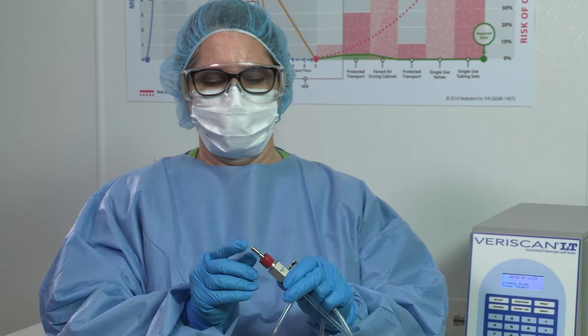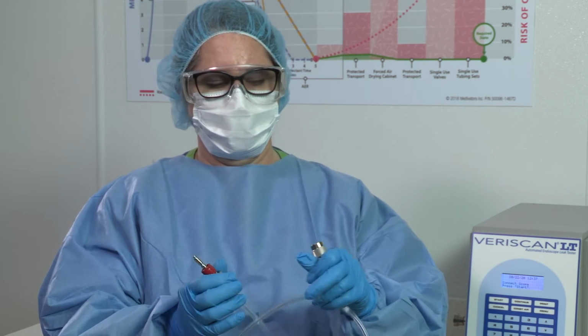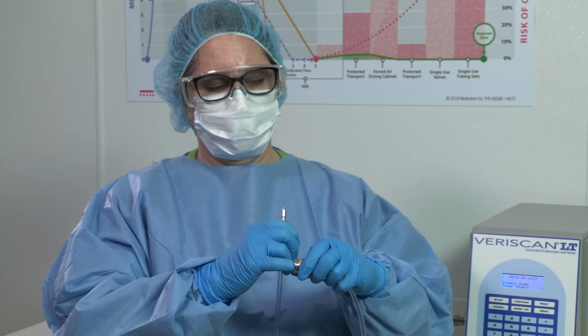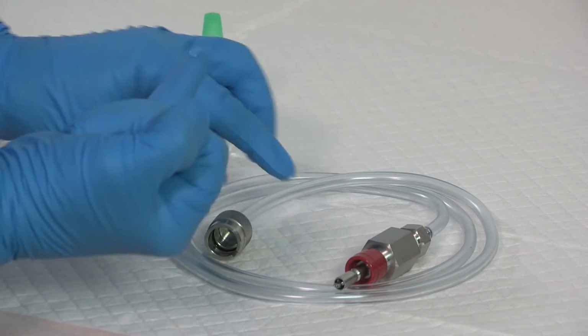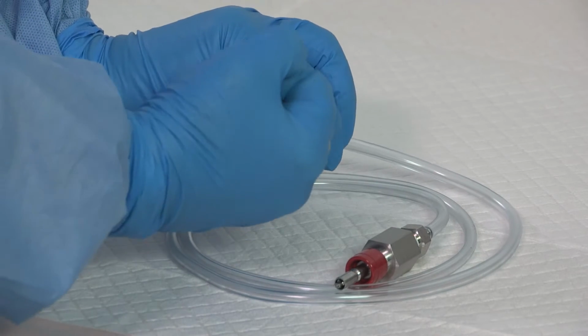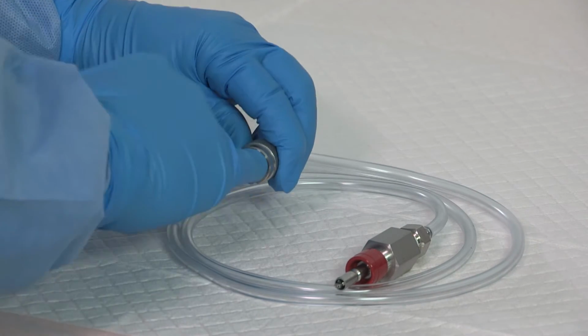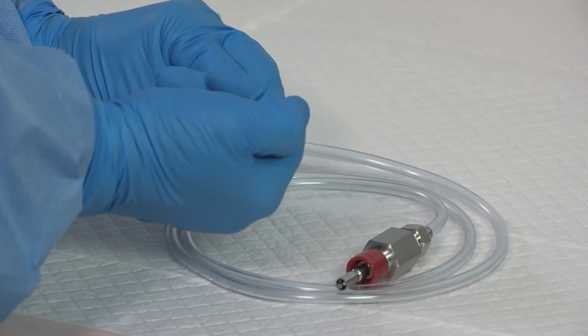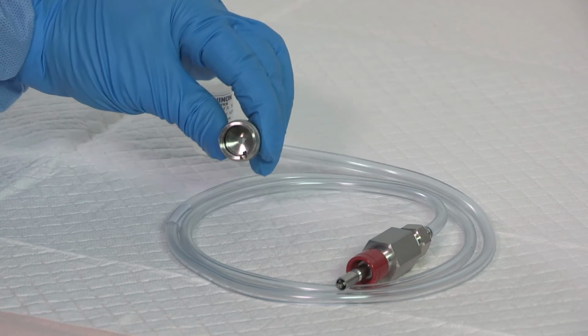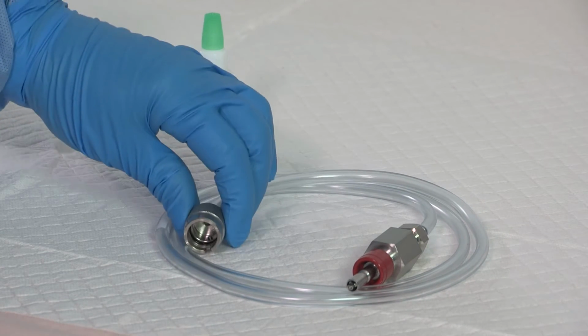A faulty quick connect tubing can result in a false endoscope leak test, identified as a fail condition during the leak test. Locate the O-ring in the endoscope connector end of the quick connect tubing and with a gloved fingertip, lightly lubricate with silicone oil. Lubricate lightly to ensure a secure connection. Failure to lubricate the O-ring can result in a false endoscope leak, identified as a fail condition during the leak test.